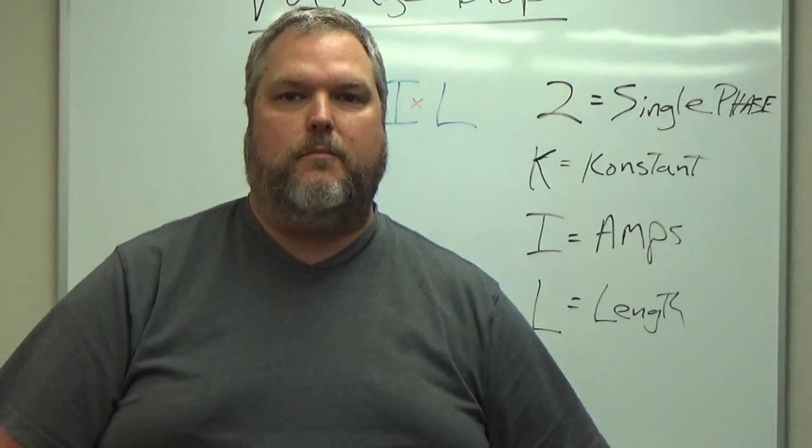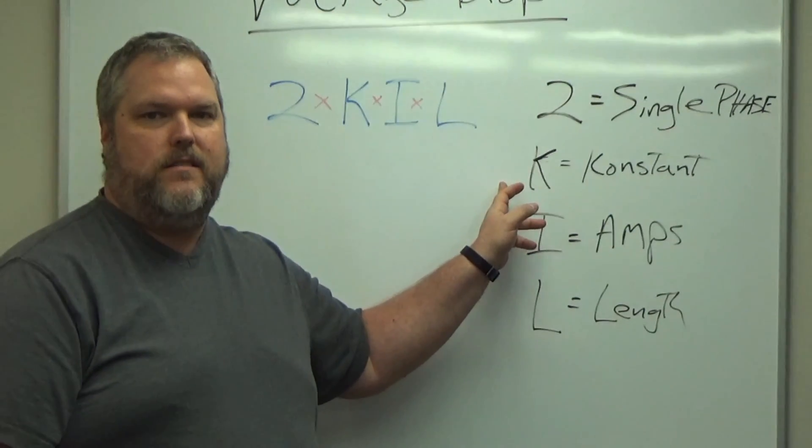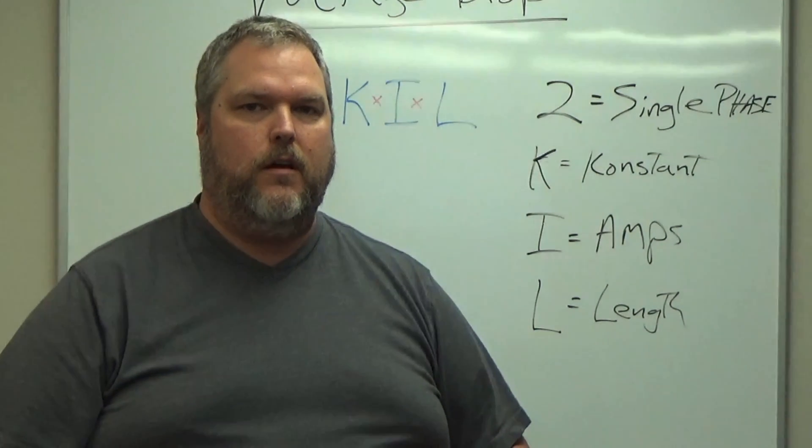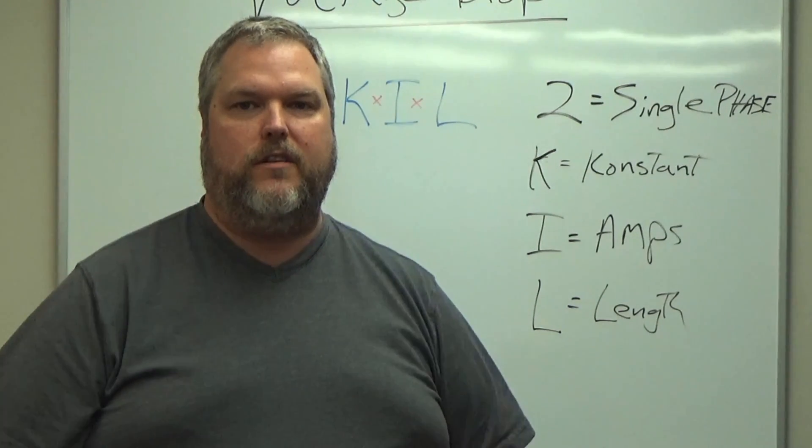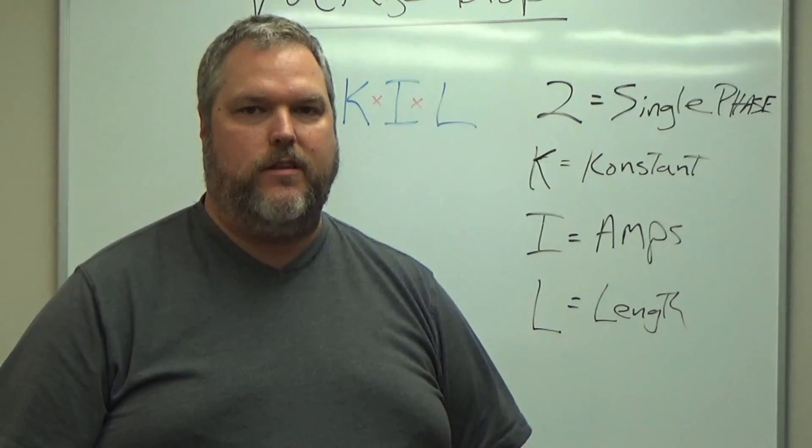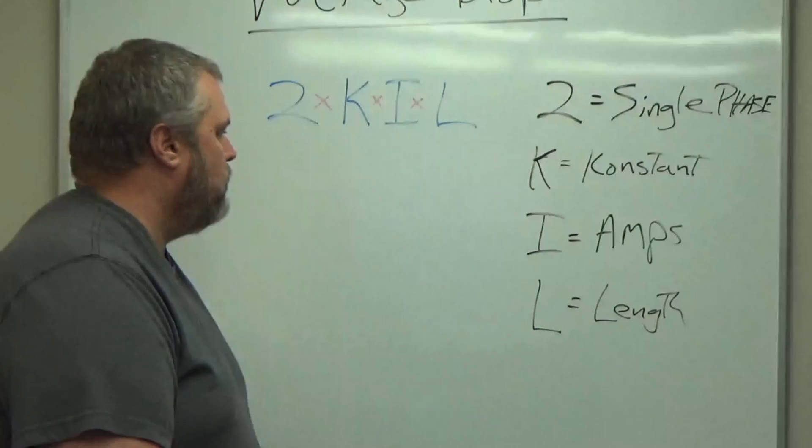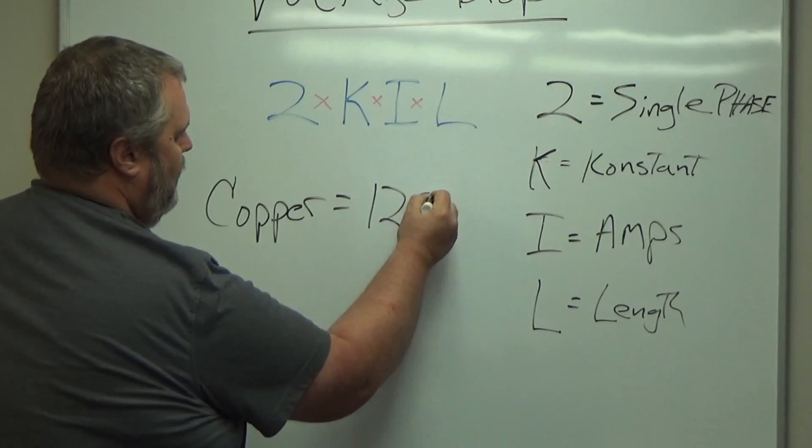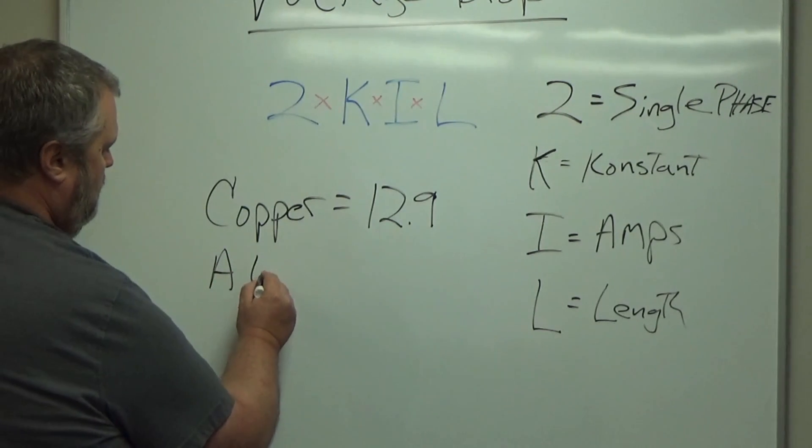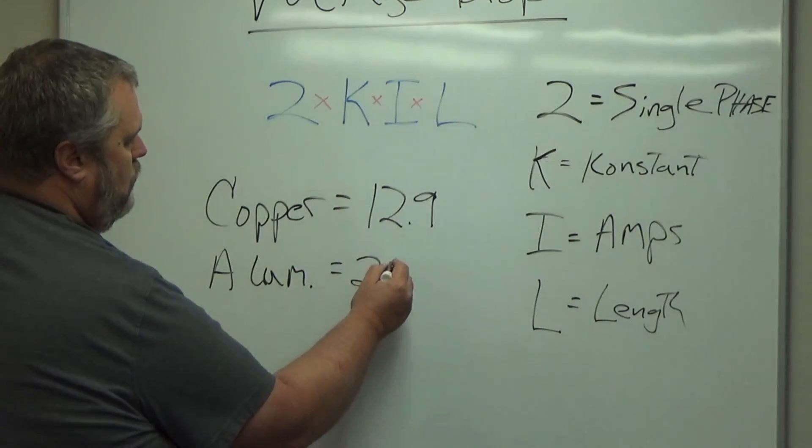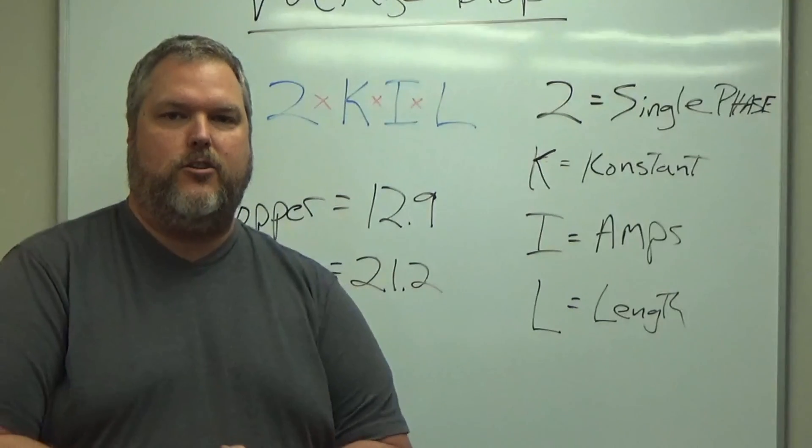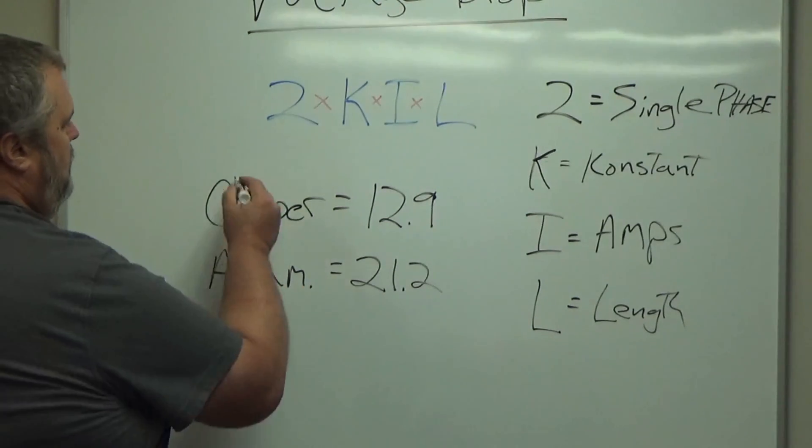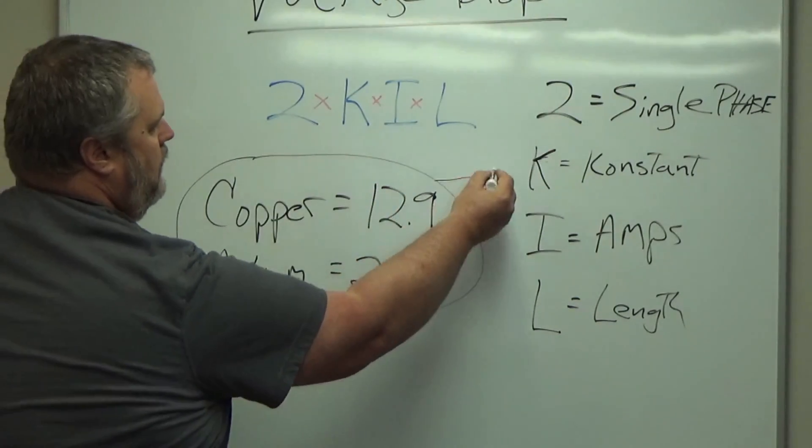The reason I want to start with this is because there's a couple things you need to know. One of the biggest things is the constant. The constant is going to stand for the type of wire we're going to pull. We have to go over aluminum because you can pull aluminum, but we're going to need to know the difference between aluminum and copper. So when we deal with K, copper equals 12.9 and aluminum equals 21.2. A lot of information, but what we need to remember is this is equal to K, the constant.